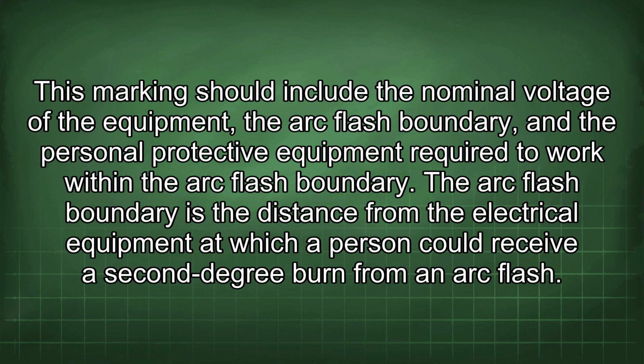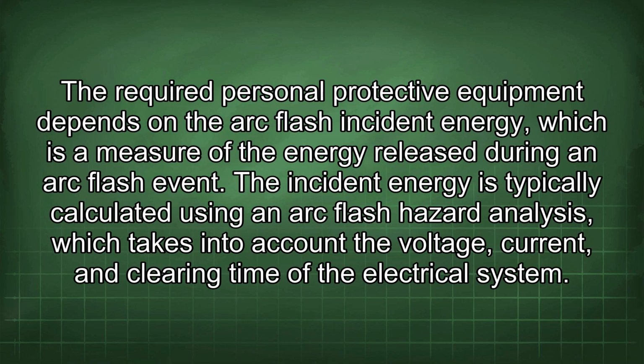The arc flash boundary is the distance from the electrical equipment at which a person could receive a second-degree burn from an arc flash. The required personal protective equipment depends on the arc flash incident energy, which is a measure of the energy released during an arc flash event.